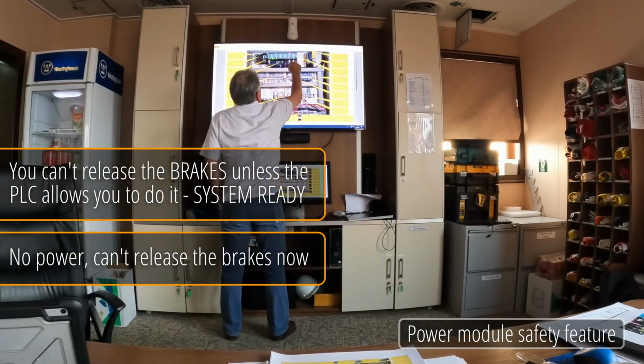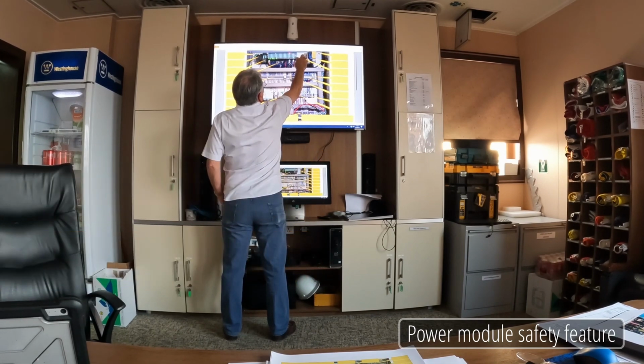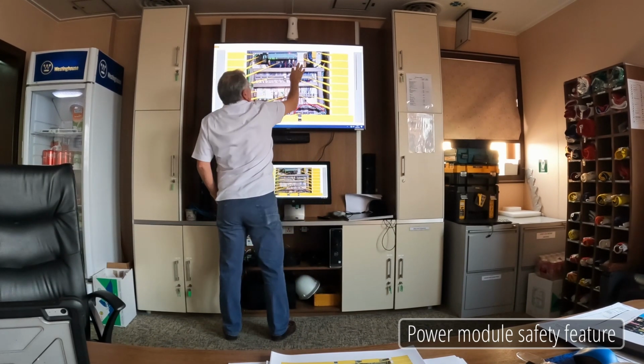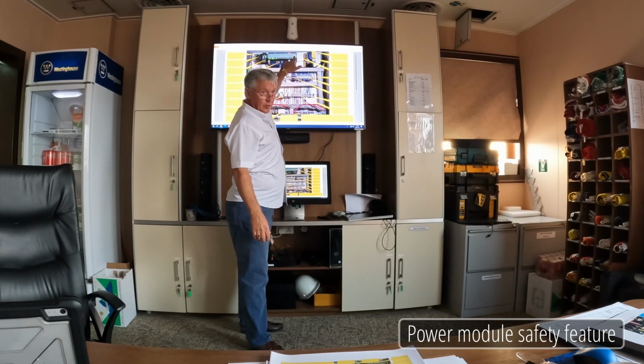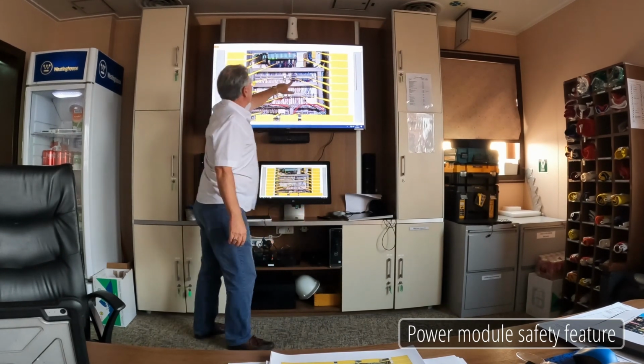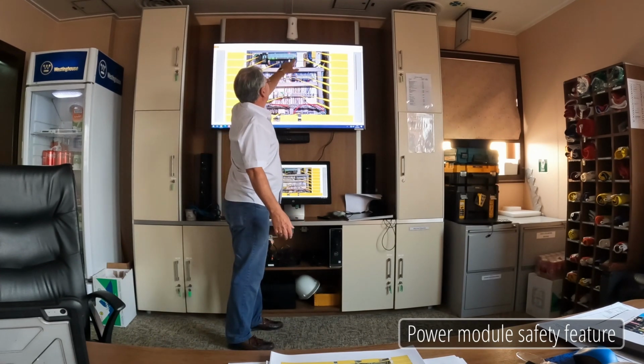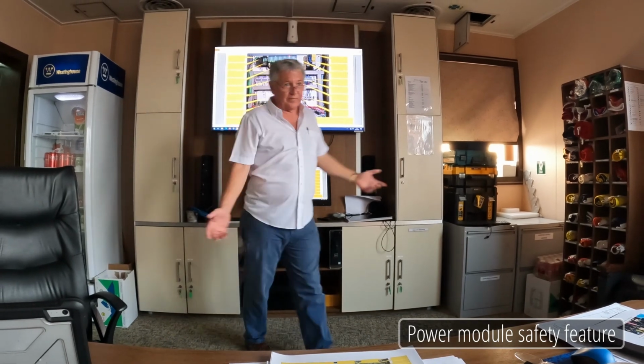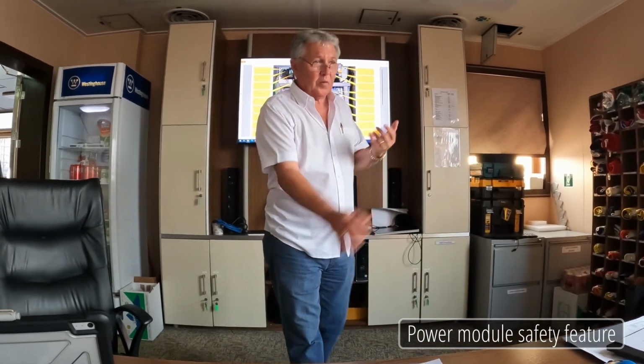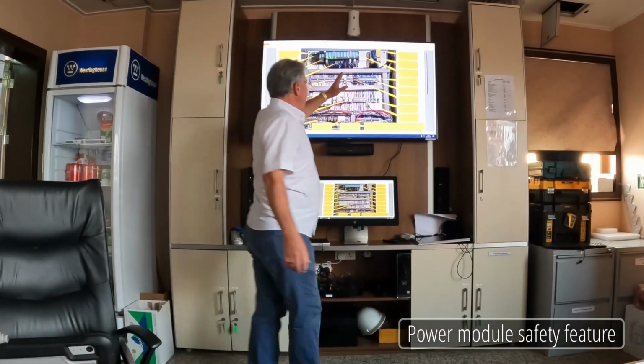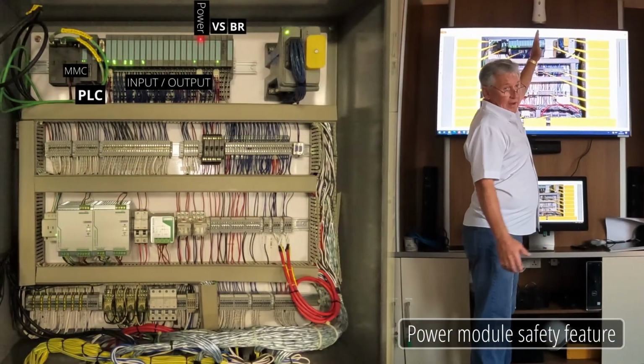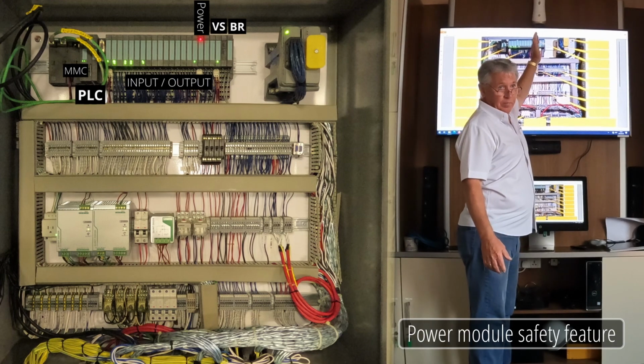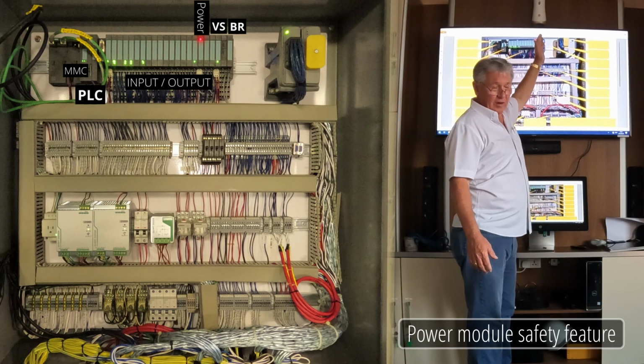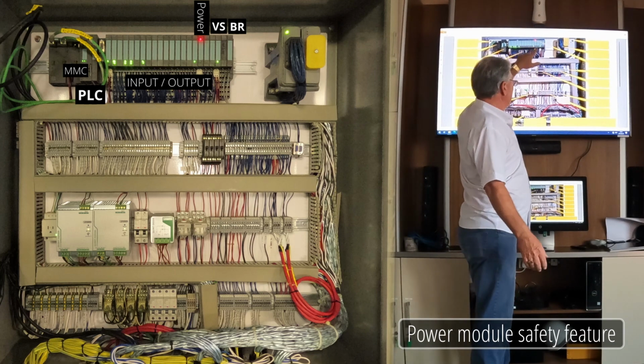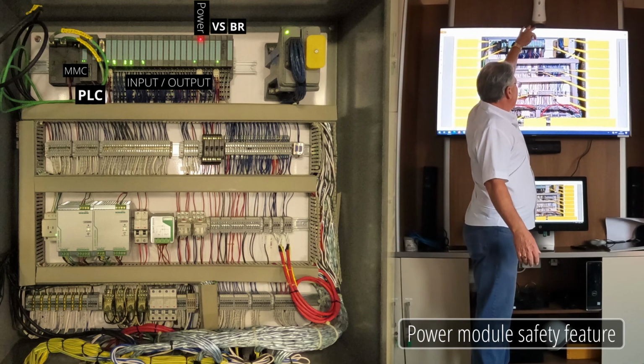So these 2 modules run the brake solenoid. Now these guys run the variable speed solenoid, I do not manage that power. So if these guys explode, or some short circuit happens and the circuit breakers don't work and we fry this, the only thing we fried was the variable speed. We didn't hurt anything else, we didn't break the brakes, we didn't break the system, we didn't hurt the analog inputs, we didn't blow up all the transducers. So this is all protectionary stuff for what I call the dangerous stuff. Solenoids are dangerous, I mean, it's a coil of wire, anything can happen to it.